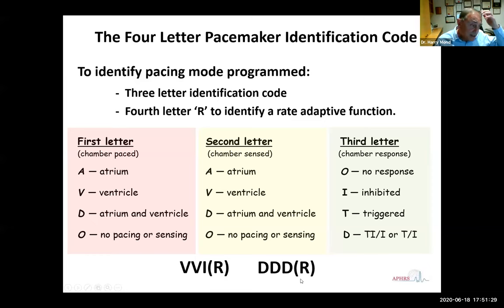For DDD pacing, we have dual pacing: in the first letter, paced in atrium and ventricle. The second letter is also sensed in atrium and ventricle. And the third letter indicates inhibition in both the atrium and ventricle. But what it also denotes is that there is triggering of the atrium causing the ventricle to then fire off after an appropriate AV delay. So the D there not only looks for inhibition of the atrium or the ventricle, but also for triggering of the ventricle.